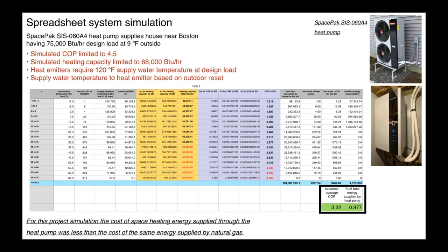And we actually looked at this and we compared the price of energy being supplied through this heat pump to the price of natural gas. We actually found that the heat pump was producing energy at a lower cost in dollars per million BTUs supplied than gas was in that market. And that's significant because oftentimes today, when we look at alternatives to natural gas, some of us throw our hands up and say, well, they've got natural gas service. You know, we can't compete with that, with anything else, whether it's fuel oil or pellets or solar thermal, whatever. Not the case here. And I believe in that area where this model was produced, electricity was running about, I think it was 14.7 cents per kilowatt hour. I honestly don't remember what the gas price was, but very competitive situation here.